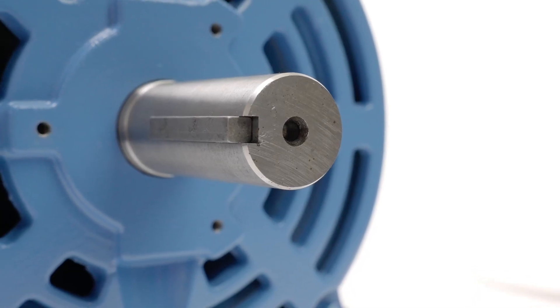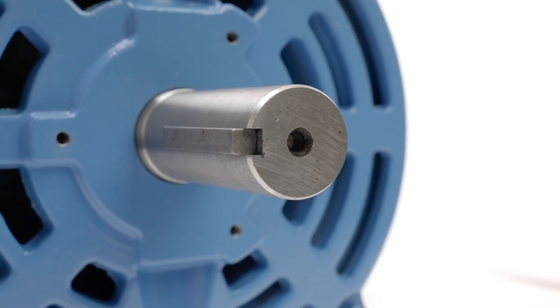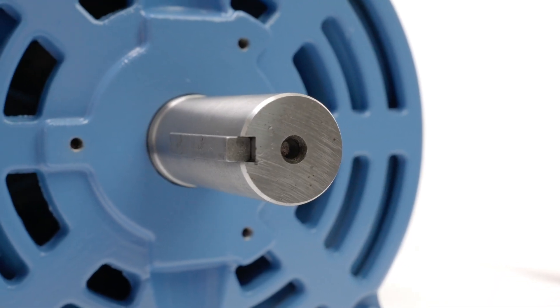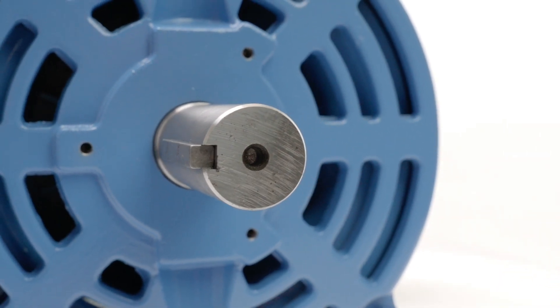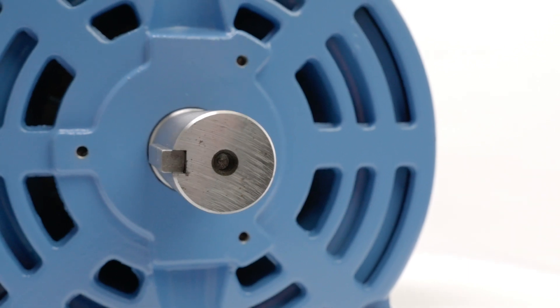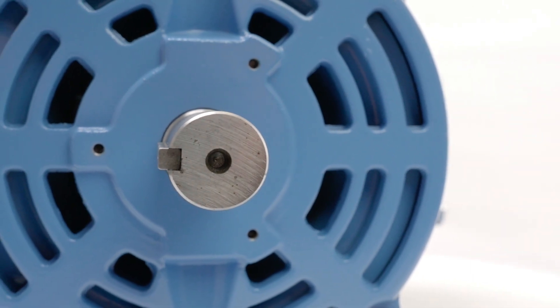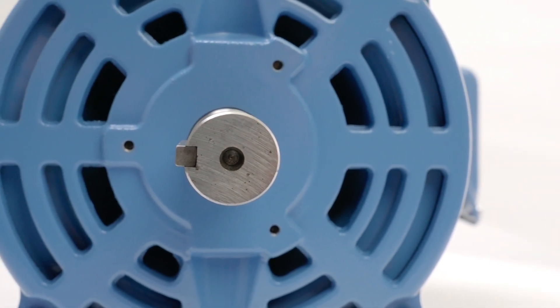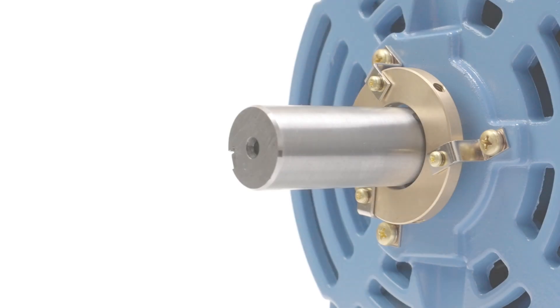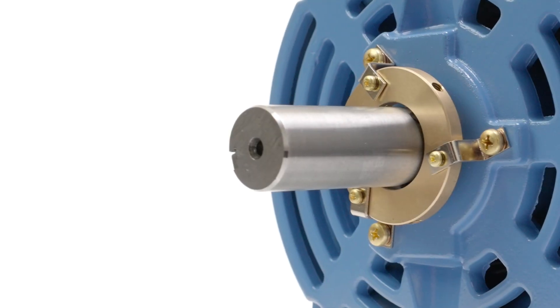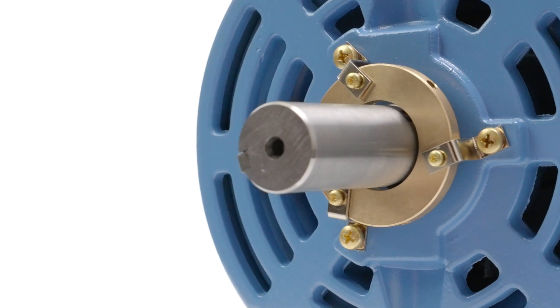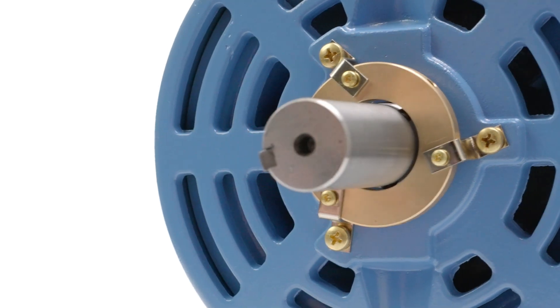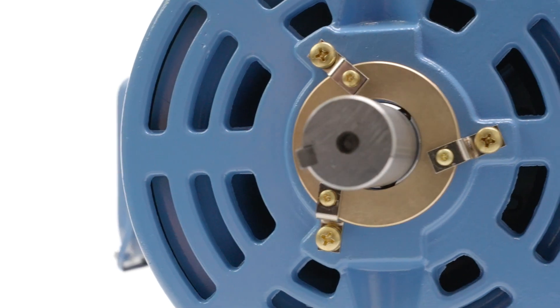All Worldwide ODP motors with a 143 T-frame and up are pre-drilled and tapped to accept grounding rings that protect against shaft currents. External grounding rings allow testing and replacement without the need to open the motor housing, simplifying service and reducing downtime.